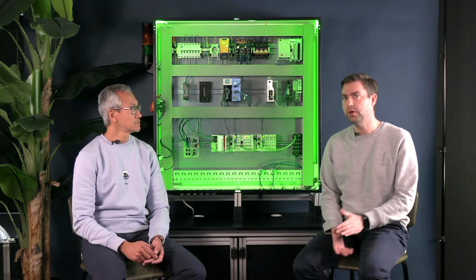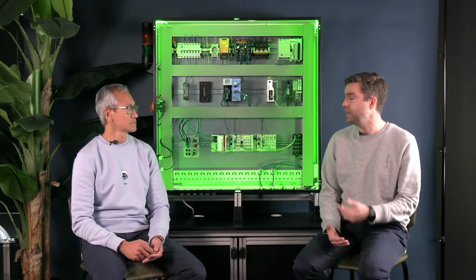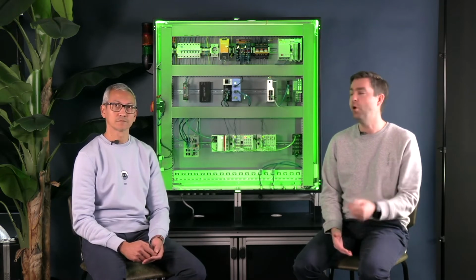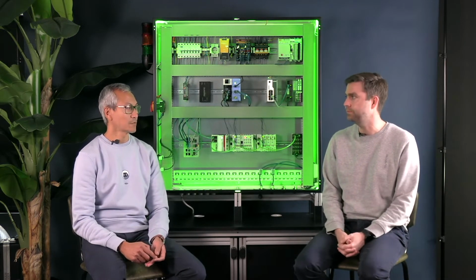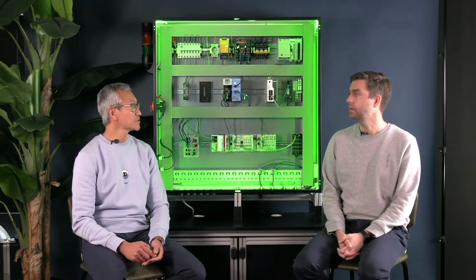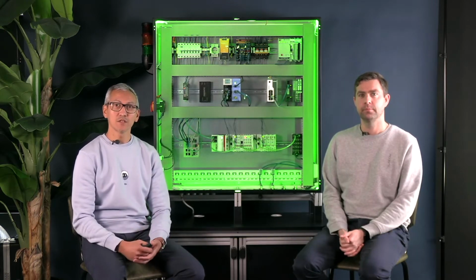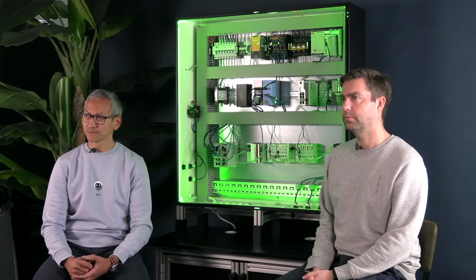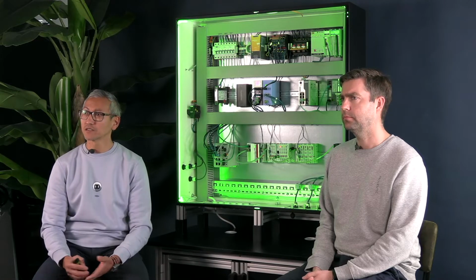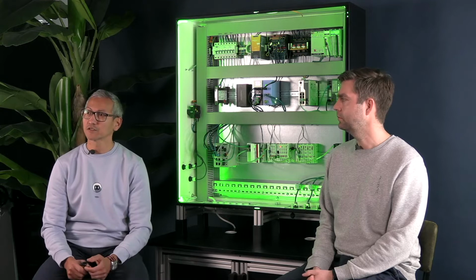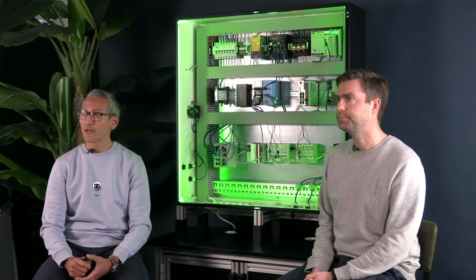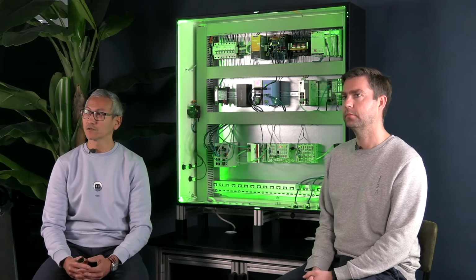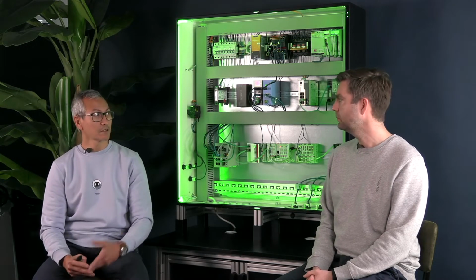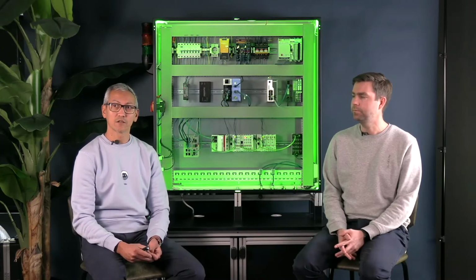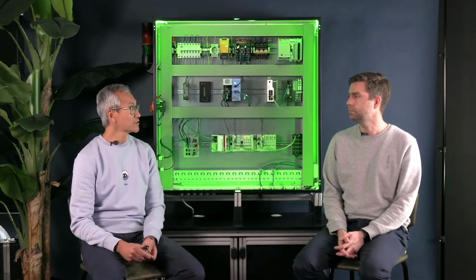So would you say then, Fedor, if you want a quick and easy redundant system implemented within your PROFINET networks, MRP is the best way to go as the first step? Yeah. The easiest and probably also the cheapest one. Okay, and that's very important as well. Most important. So, looking at MRP, the Media Redundancy Protocol, it is standardized by PROFINET, and a lot of switches implement MRP. It's basically using two lines going around, so you get a ring-like topology. And when one of those cables fails, then the communication goes the other way.